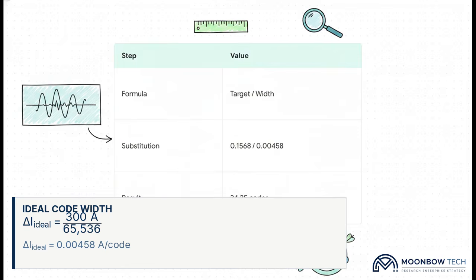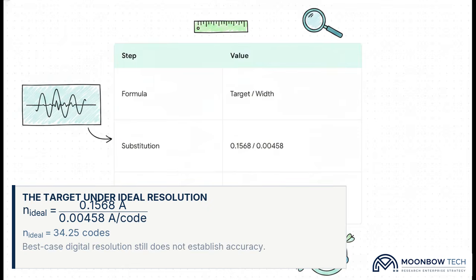Now, let's apply this ideal step size to the tiny signal we actually care about resolving. The formula is the target harmonic divided by our code width. We substitute our 0.1568 amp target and divide it by 0.00458 amps per code. The result? Our tiny harmonic spans roughly 34.25 ideal codes, 34 distinct data points to map out that little wave. Sounds like plenty of resolution, right? But remember, this is a mathematical fantasy. It establishes resolution, sure, but definitely not reality.